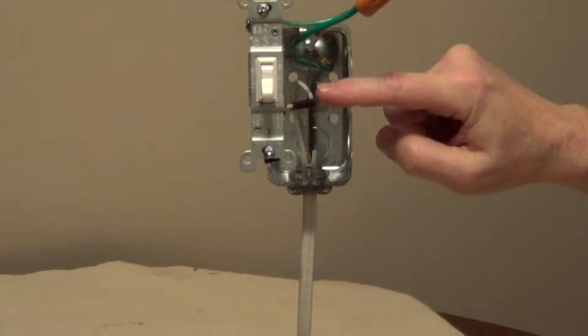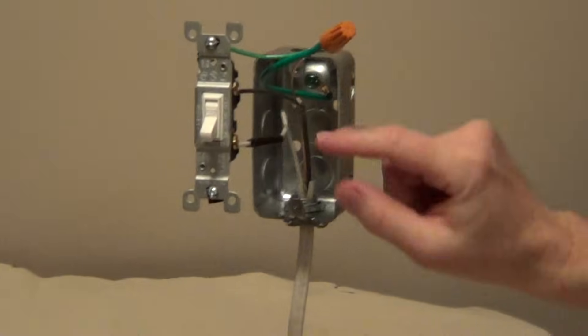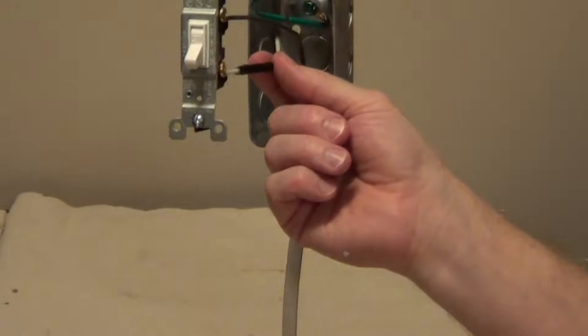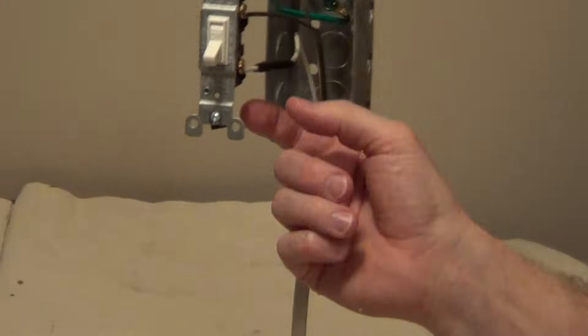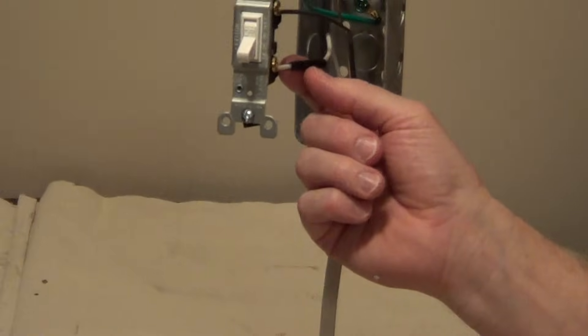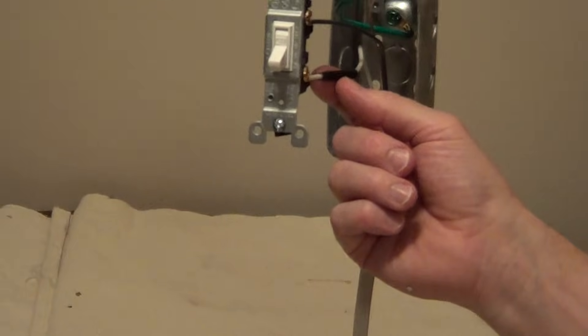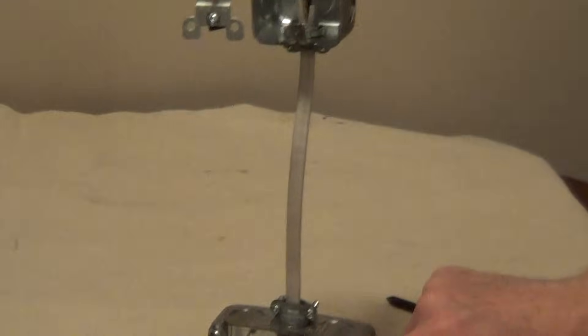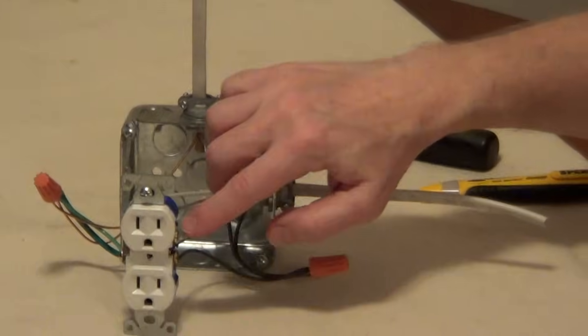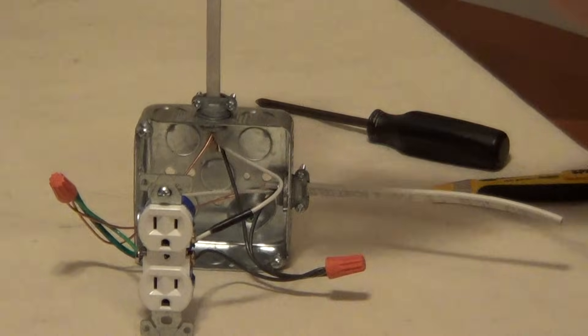Now from the switch, because we're using a two-wire cable, this white wire, which is normally a neutral, we have to mark it with black tape to let everybody know that this is a hot wire. It comes down to the top part of this outlet and now this top part will be controlled by the switch.